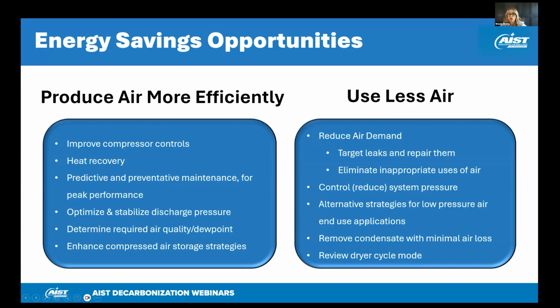And for condensate drains and dryers, they operate in two different modes. One mode is a timed mode, and another mode can be a demand mode. If you select the demand mode option, you're definitely going to save dollars, and you're going to save compressed air, and you're going to save power.